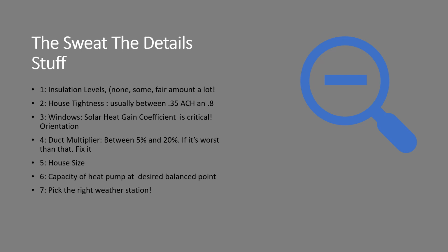Capacity of the heat pump, the desired balance point, we're using a 30-degree balance point. And again, you have to look at the detailed capacity tables provided by the manufacturer. And oh yeah, number 7, make sure you pick the right weather station.